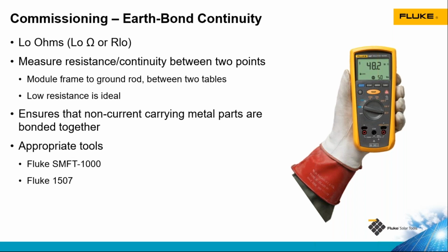There's an IEC standard that requires a 200 milliamp test during this procedure. Most multimeters, when you're testing continuity, will only test at 50 milliamps. So you need a tool that has this specific test type. We have 2 tools at Fluke that can do this. The SMFT 1000 can do this earth bonding test at 200 milliamps and save the results and report that out later. And the 1507 insulation resistance tester can also do this test at 200 milliamps.